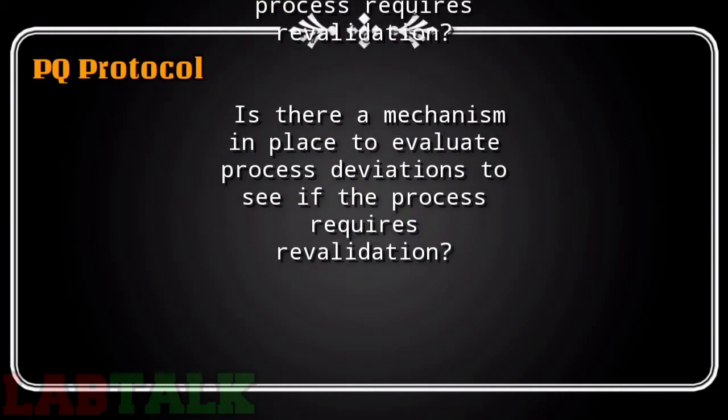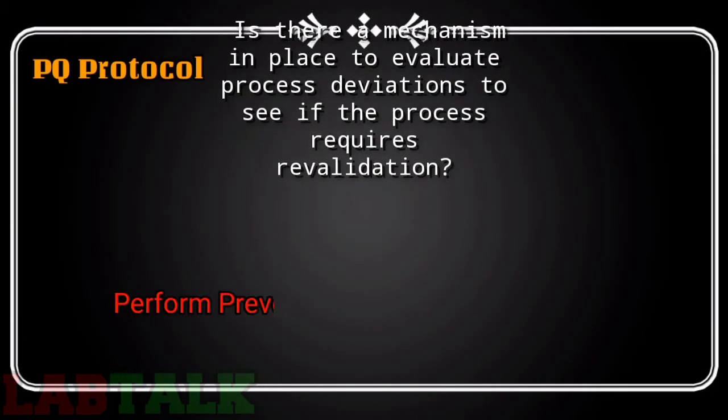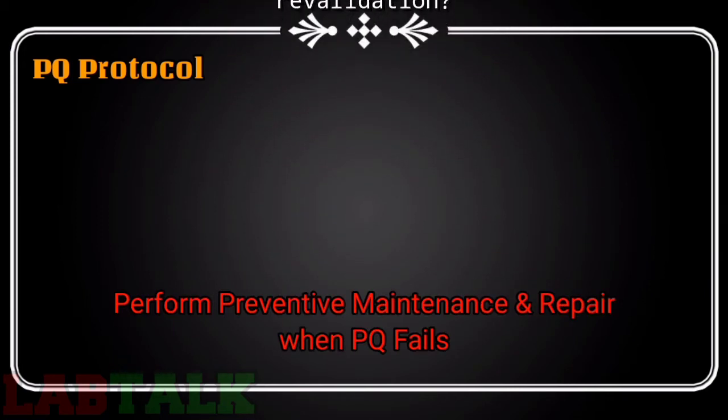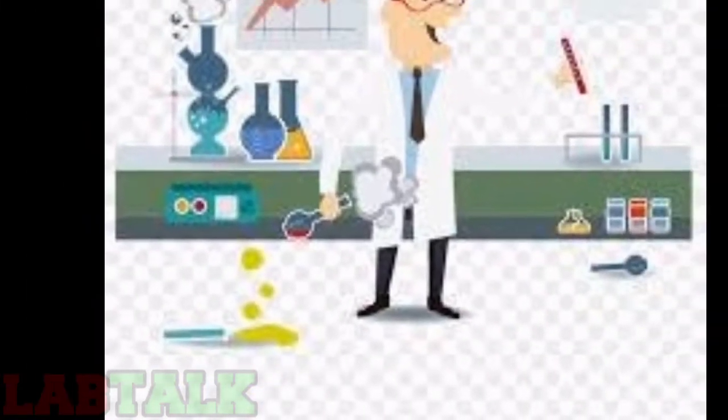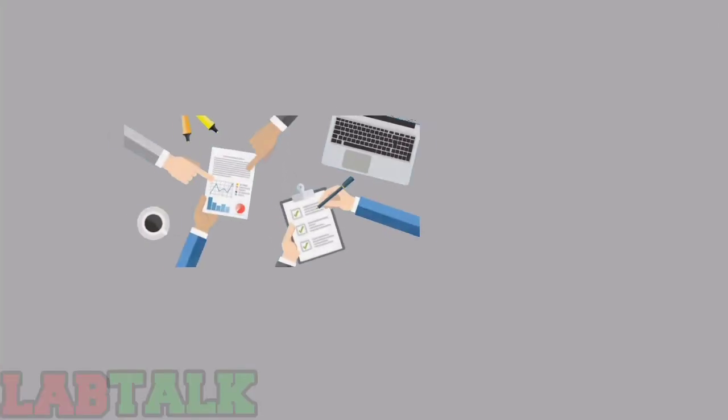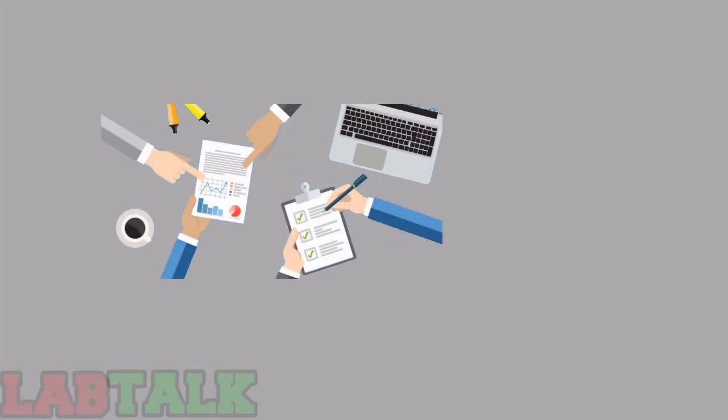Preventive maintenance and repairs should be performed when a PQ test fails to meet specifications. The instrument requires maintenance or repairs. Now, how to prepare a PQ report or what are the contents of the PQ report? The documentation of the PQ report is most important and is a continuous process.